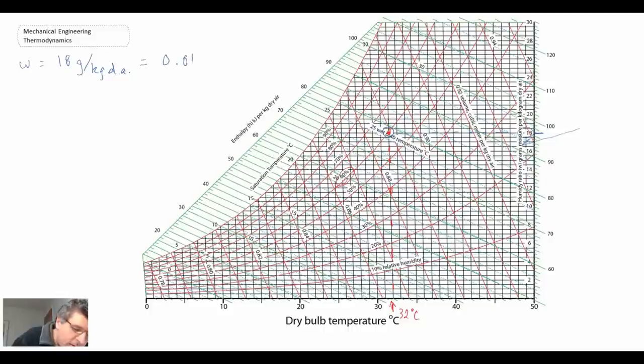So that becomes our specific humidity. The next thing they want us to get is the enthalpy. And enthalpy are the green lines going up, and so here are the enthalpy data on the side. So if we move our way up here, we find a value somewhere around 79. So that's kilojoules per kilogram of dry air.